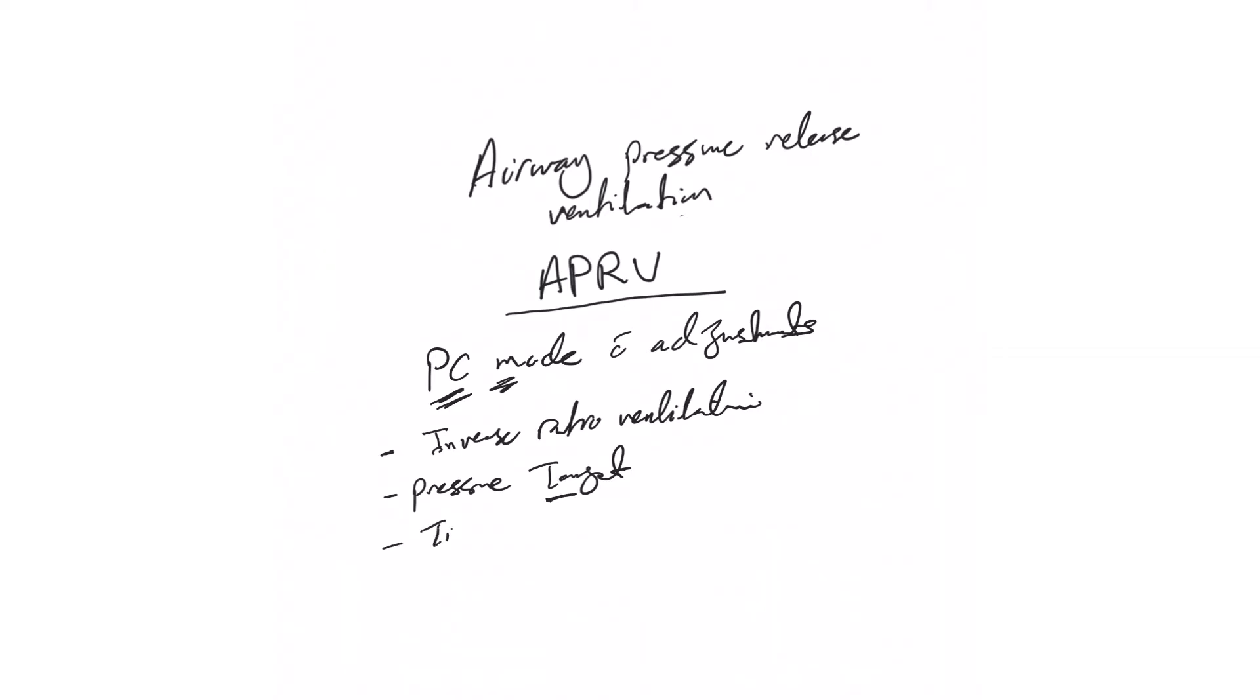And this is the difference: in pressure control, the traditional one, we have continuous mandatory ventilation. This is an intermittent mandatory ventilation. Continuous means that every single breath the patient tries to take will be supported by the ventilator exactly like all other breaths. Well, intermittent mandatory ventilation: only the number of breaths we provided—the ventilation, let's say 10 breaths a minute—only those will be supported. Any extra breaths will not receive the same support; may receive less support or pressure support.